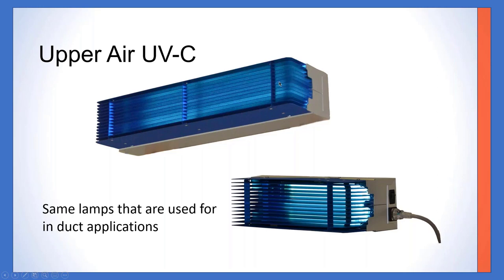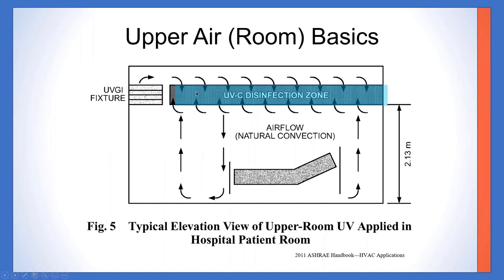Now, these are non-reflective baffles. They will not reflect that energy, so you're collimating a beam that comes out. We've been using them mainly around patient rooms, but we've also been seeing them in daycare centers, lobbies, cafeterias, places like that, and I'll show you some pictures. It's sending a collimated beam of UV disinfection up across the ceiling, and as the convection of the air in that room moves either from supply to return, or just pure convection, it's going up into the kill zone.